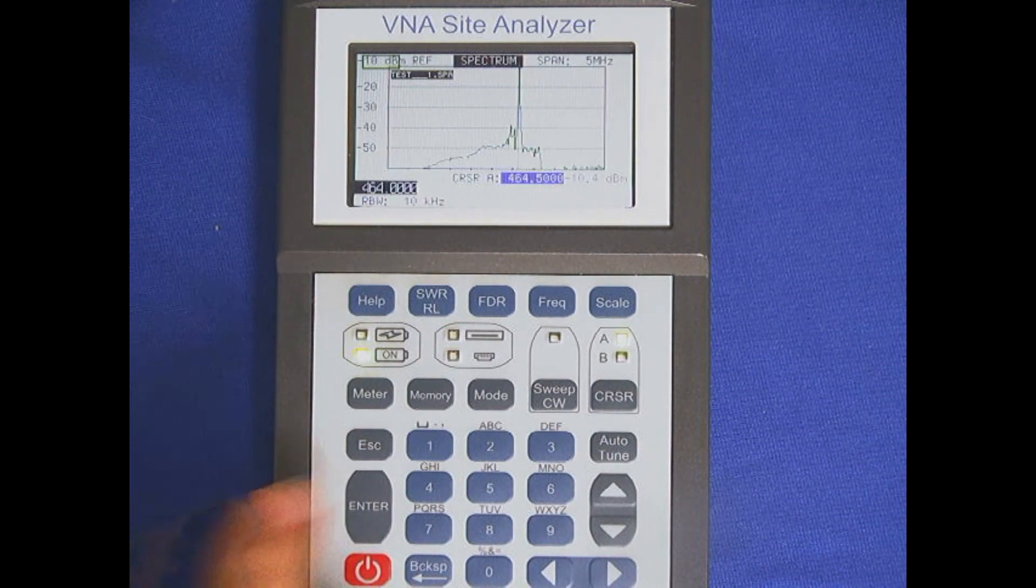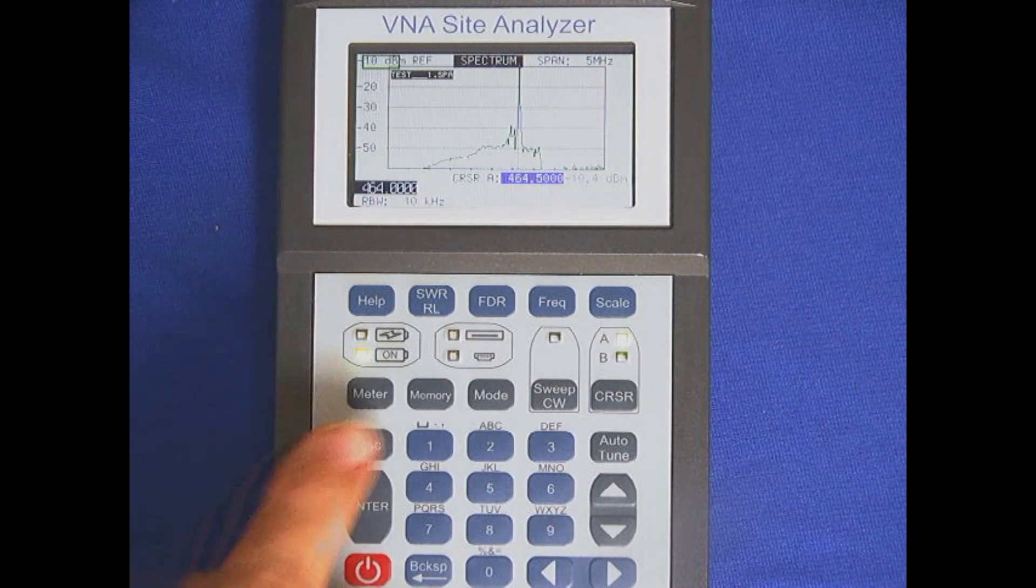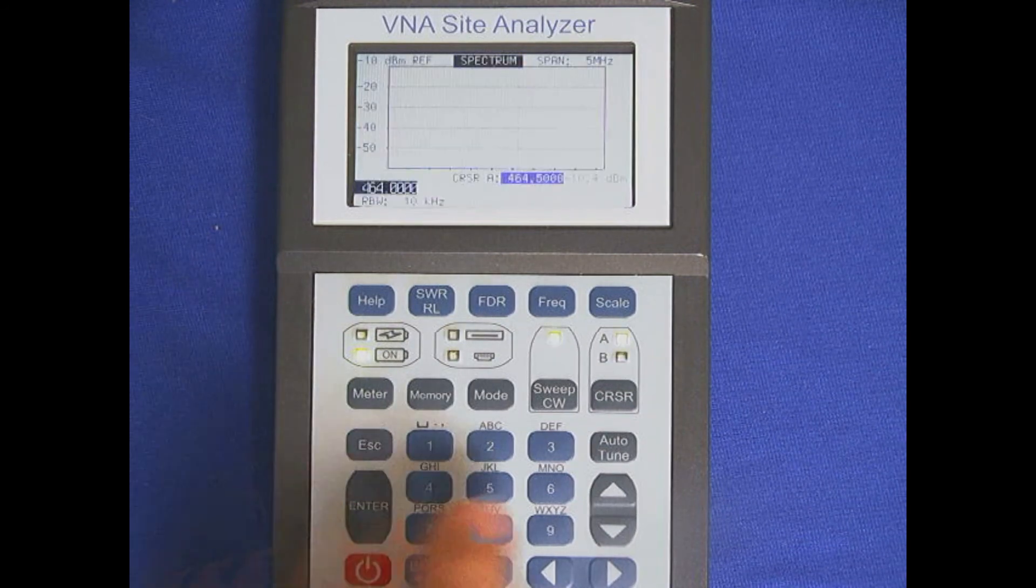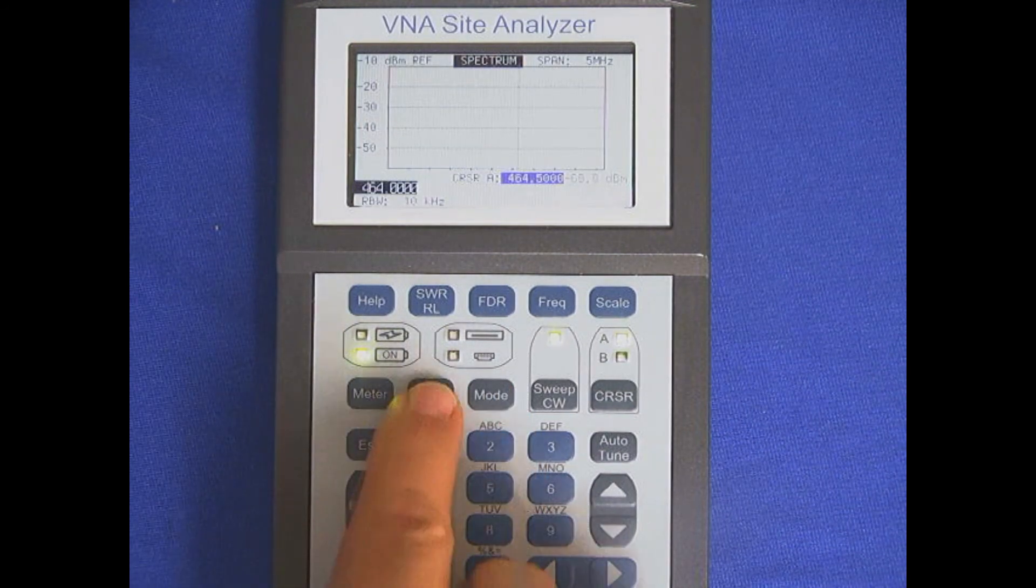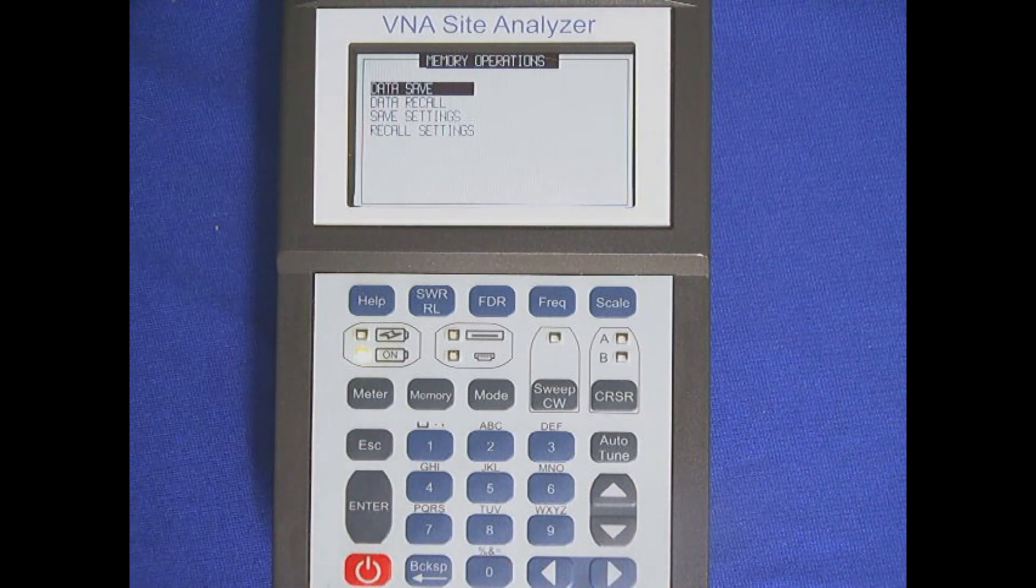I can also save my setups the same way here in memory. Can't do it from the test page. Got to escape. I can save my setup by hitting memory and then selecting Save Settings and naming the settings. This would be a spectrum analyzer in the UHF 460 range.